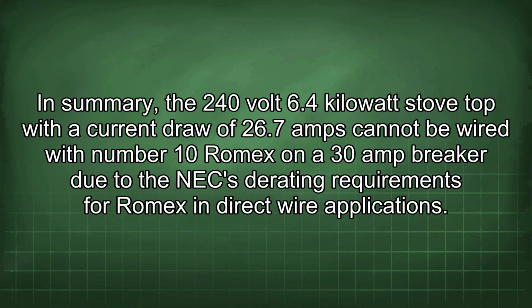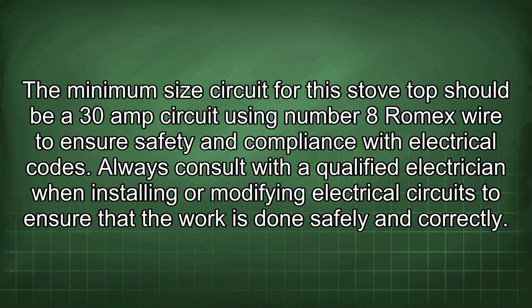In summary, the 240-volt 6.4 kilowatt stovetop with a current draw of 26.7 amps cannot be wired with number 10 Romex on a 30 amp breaker due to the NEC derating requirements for Romex in direct wire applications. The minimum size circuit for this stovetop should be a 30 amp circuit using number 8 Romex wire to ensure safety and compliance with electrical codes. Always consult with a qualified electrician when installing or modifying electrical circuits to ensure that the work is done safely and correctly.